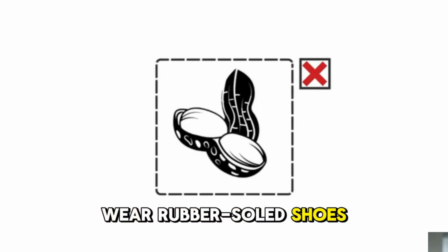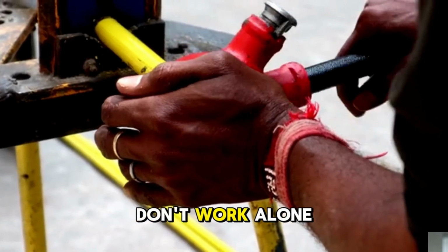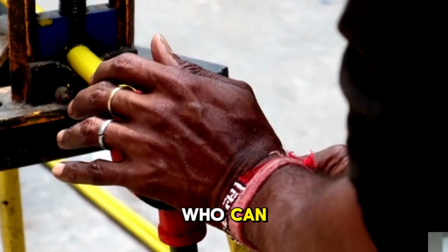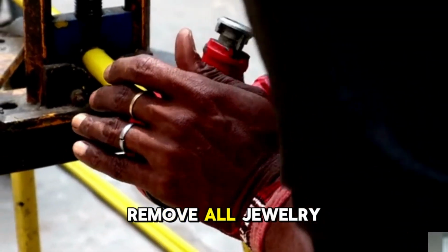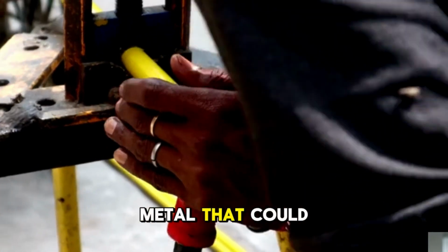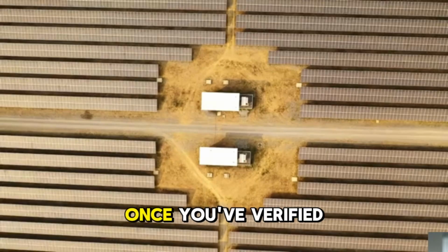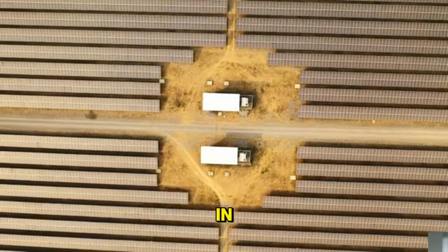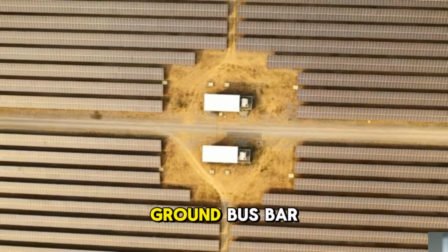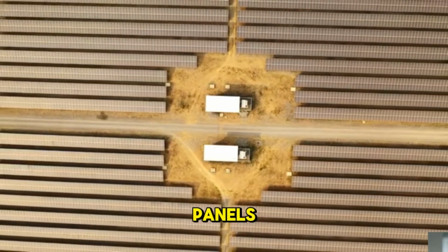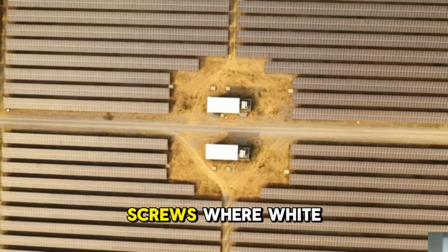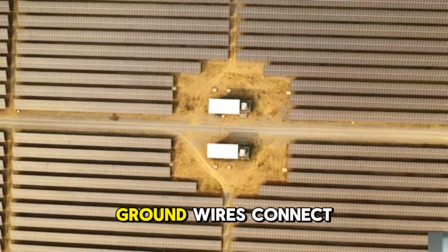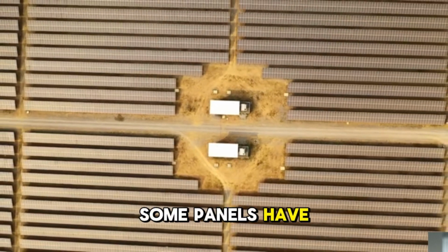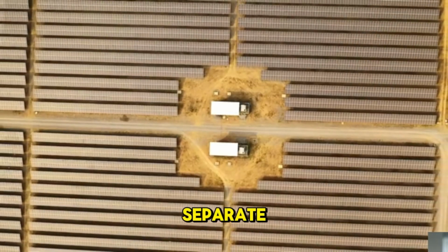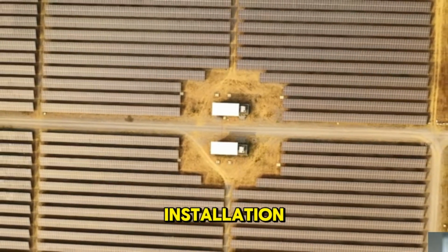Wear rubber-soled shoes. Work on a dry surface. Don't work alone if possible. Have someone nearby who can call for help if needed. Remove all jewelry, watches, and anything metal that could create an accidental short circuit. Once you've verified the panel is safe to work in, locate the neutral bus bar and the ground bus bar. In most residential panels, these are metal strips with multiple screws where white neutral wires and bare ground wires connect. Some panels have these bonded together, others keep them separate. Either configuration works for this installation.